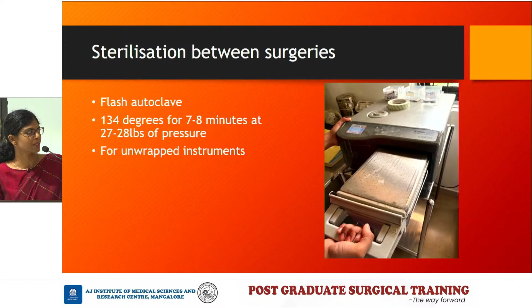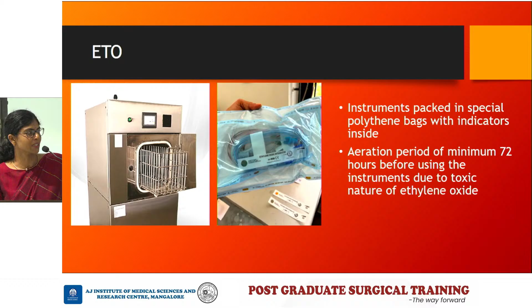Now, coming to ETO or ethylene oxide sterilization, this is done usually once a month or twice a month in most OTs. Those instruments which have wires on them, like your diathermy probes or cryoprobes, these are the instruments which cannot be autoclaved but can be sterilized with ETO sterilization. So the instruments are packed in special polythene bags with indicators inside. And you have to remember that this ETO gas is very toxic. So an aeration period of minimum 72 hours should be there before you use these instruments.